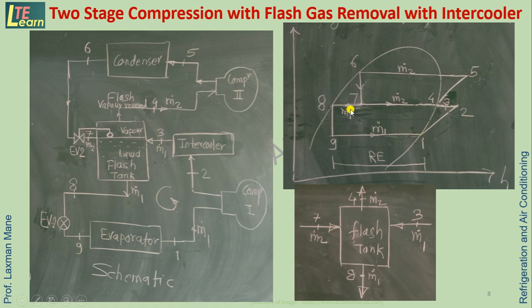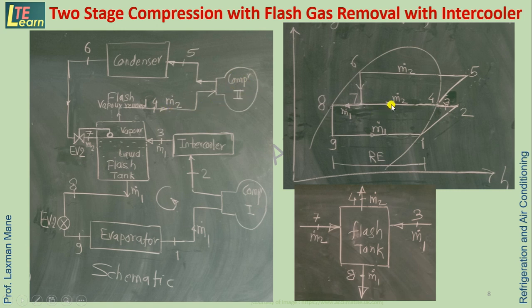Mass flow rate m1-dot passes through the evaporator and circulates in the lower loop: from the flash tank through the evaporator, first compressor, and intercooler. Mass flow rate m2-dot is the flash vapor removed, which passes through compressor 2, then the condenser, circulating in the upper loop. So m1-dot circulates in the lower envelope (points 1-2-8-9) and m2-dot circulates in the upper envelope (points 4-5-6-7).